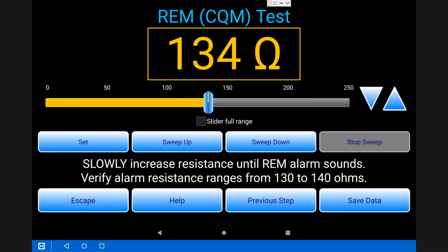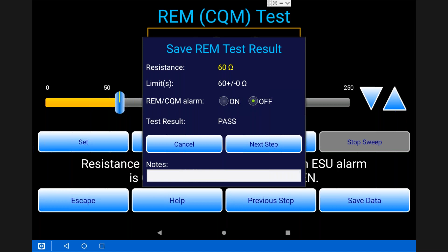At this next step, we now need to slowly increase the resistance from 120, and we are looking for an alarmed value. So I'm going to go ahead and increase the resistance. Again, I know we're simulating this here, so I'm going to say at 134, I hear the audible tone, the red light turns on, I now have an alarm. So I'm going to indicate that at 134, I have an alarm, it is on, and that is a pass because it's between 130 and 140 ohms, and next step. Next, we automatically switch directly to 60 ohms. There's nothing the technician needs to do. I merely have to hit the save data, indicate that again at 60 with a reduced resistance, the alarm is back in an off state, and next step.